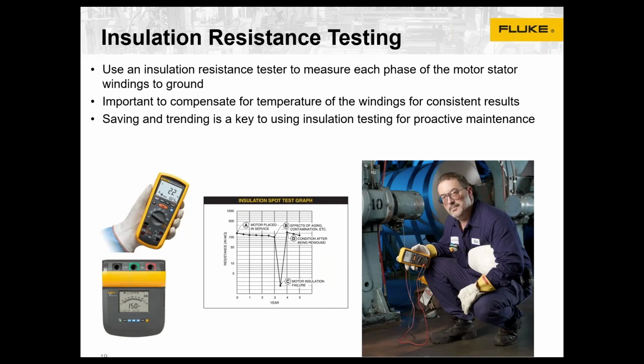Insulation resistance testing, that's another area in which you might be using this type of tool, but maybe not in a proactive fashion. A lot of people use insulation resistance testers or megohmmeters when they have a motor issue or a motor failure, a breaker trip, motor overheating. They will actually do an insulation resistance test to see: is my insulation on the windings breaking down or not? Well, you can also use this proactively over time when you take motors offline to look at and trend that insulation over time and look for evidence of a knee in the curve or a drop off to be able to better predict when it might be good to either take this motor out of service, have it replaced, or have it rewound.